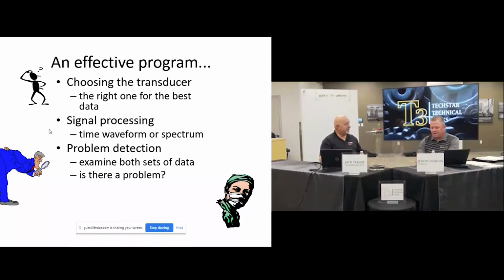We spend a lot of time talking about condition monitoring software, and a lot of people invest a lot of time and money into these really high-end, very capable systems. But that software is only as good as the data that it's being fed. Absolutely. And if you use the wrong sensor in the wrong application, or your sensor is not set up correctly, not verified, or maybe not functioning within spec, the data you're looking at in that CMS system is going to be jeopardized. That's right.